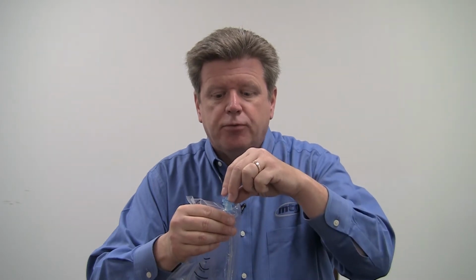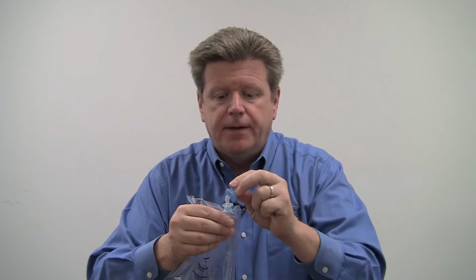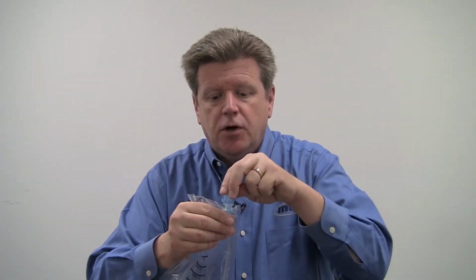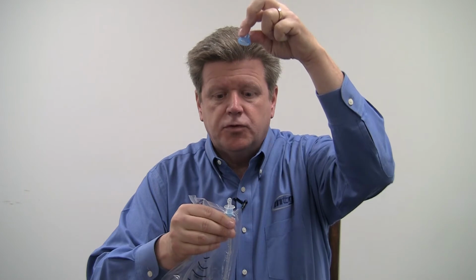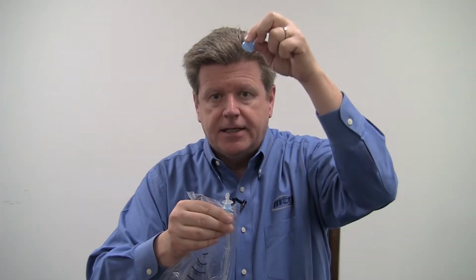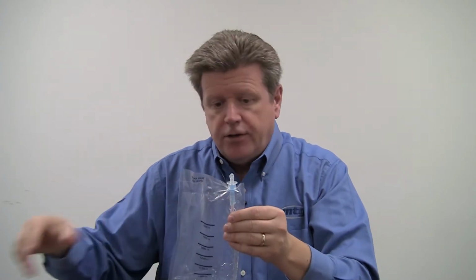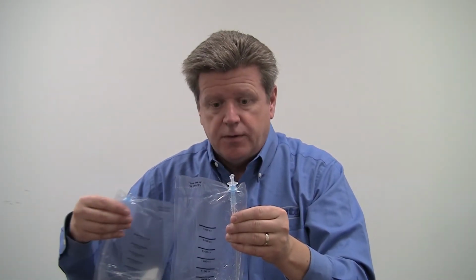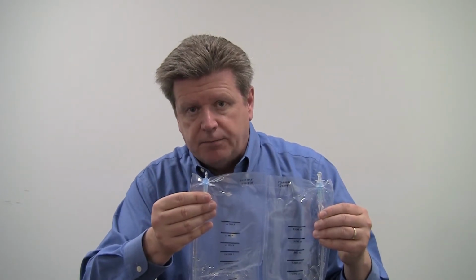It's very important when removing the cap from Instant Cath or Instant Cath Coude that you gently pry the cap off the introducer tip in this manner, okay? The reason we say to do that is you want to make sure that you always leave the introducer tip intact. You don't want to pull the cap straight away from the bag, because in some cases it can actually catch the introducer tip and pull the tip completely off. You want to make sure the tip is in place, as it is in this one on my left hand, versus the one on my right hand, which has the introducer tip completely removed.